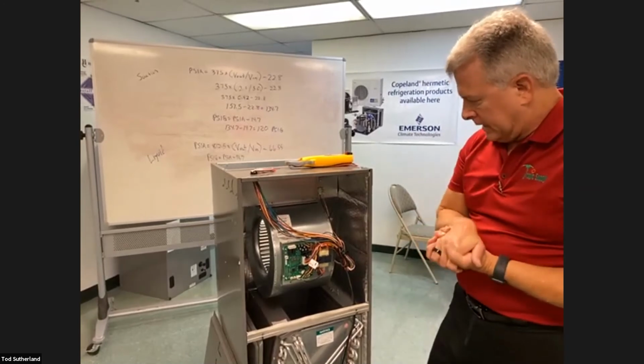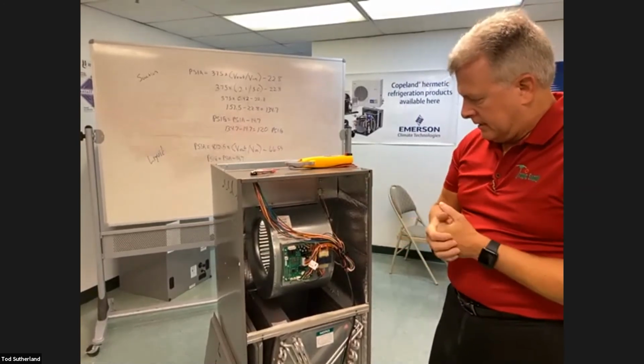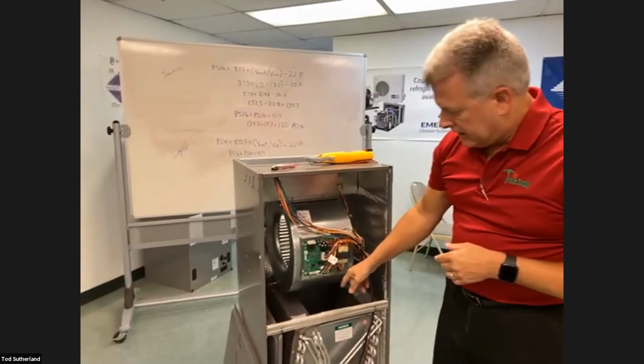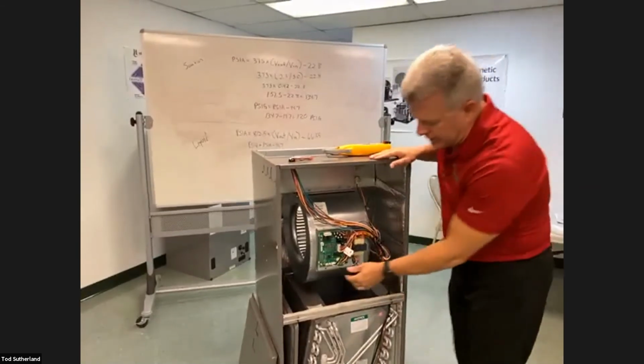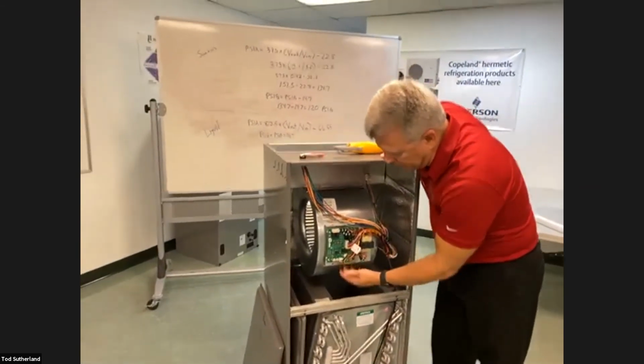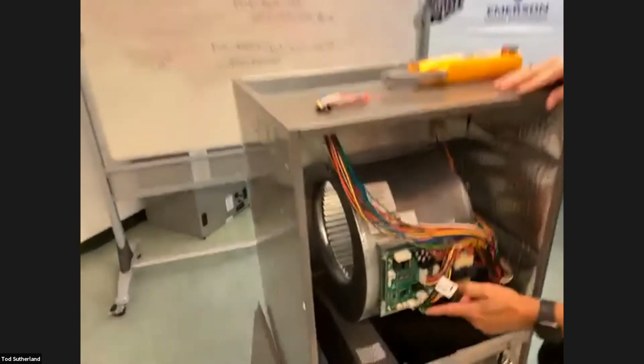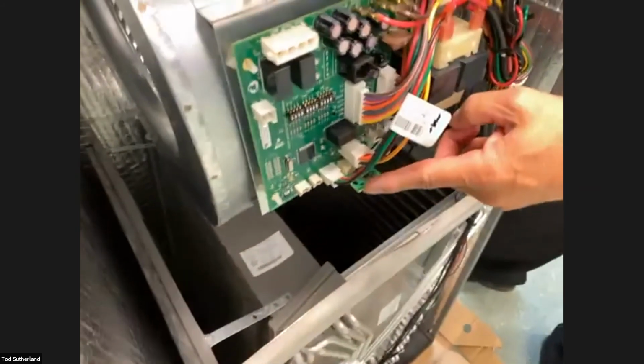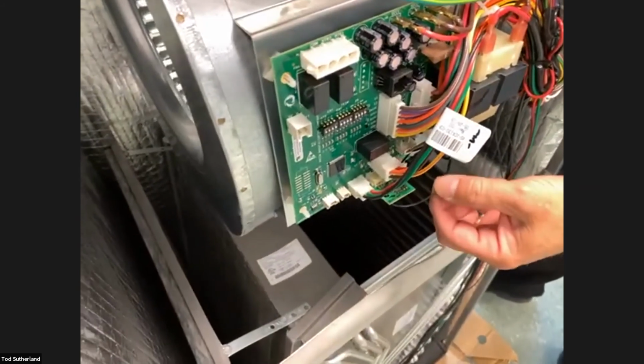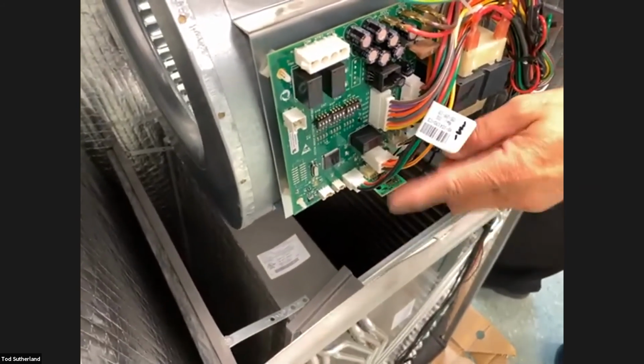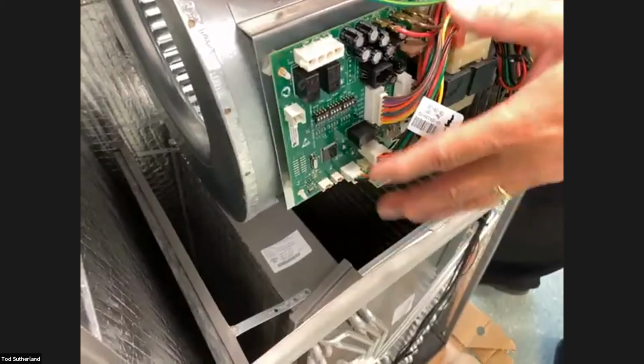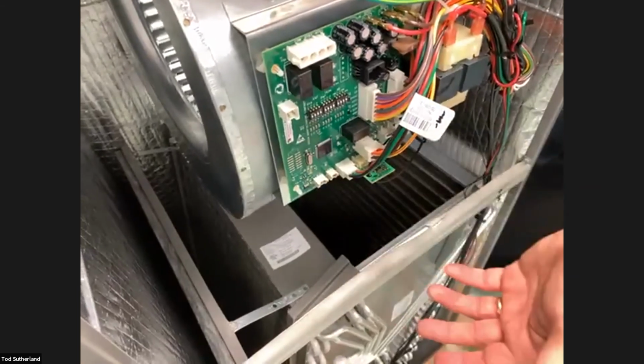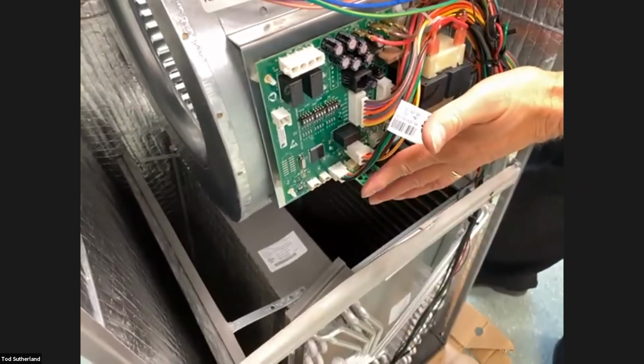Trying to think if there's anything else that I'm missing. Again, your thermistors. Oh, this communication chip on the board right here. There's one on the indoor unit and there's one on the outdoor unit. Okay. They are tethered with a wire strap because those stay with the unit. So if you have to replace the board, you're going to remove that, replace the board, and put that back in. Okay.